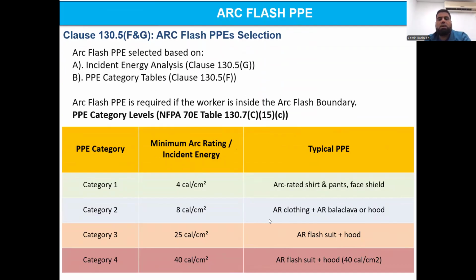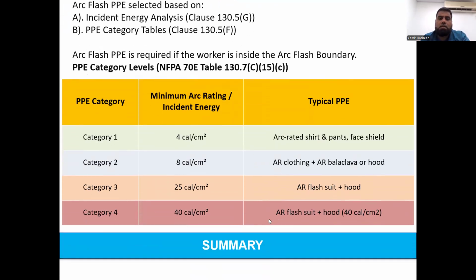So arc flash PPE is required if the worker is inside the arc flash boundary. This is the different PPE categories, category 1 till 4, depending upon the minimum arc rating and what kind of typical PPEs are required. That is also listed, like arc rated shirt and pants for category 1, and AR clothing and AR balaclava or hood, that is required for category 2. But based on the minimum arc rating and incident energy, you need to keep it in mind. PPE is required when the worker is inside the arc flash boundary, and its rating must be equal to or greater than the calculated energy. So that's our intention, and you need to keep it in mind.